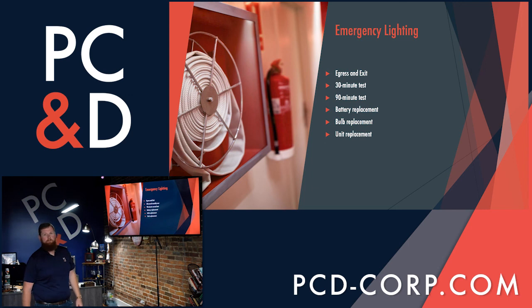All right, we'll jump over into emergency exit lighting. This lighting is manufactured to be battery backup at all time in case you were to lose power. And all we want to do is on a monthly basis, we want to check for a 30-second test, in which case I would simply go up and hit the button for the test. And as long as it illuminates for 30 seconds, it is considered a pass. If it were to fail, obviously we need to look into the bulbs or battery being needed replaced.